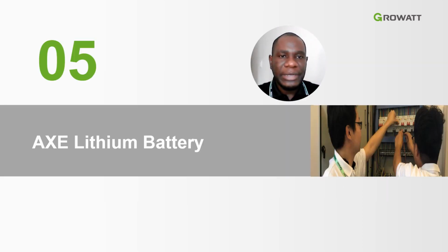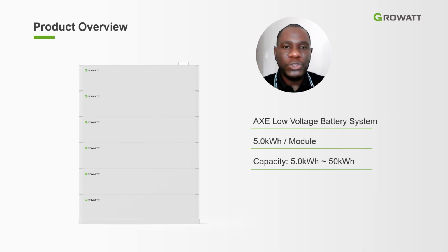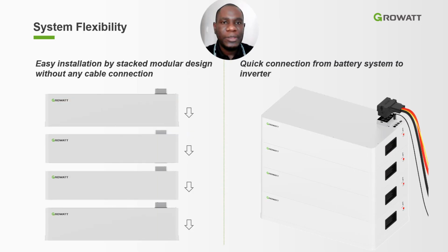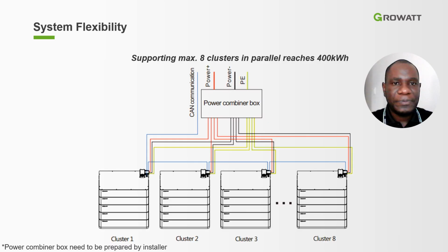The AXE lithium battery, as I mentioned before, each module has a capacity of 5.0 kilowatt hours, and you can have a cluster of up to 10 of these modules, which goes up to 50 kilowatt hour battery capacity. And this is how you connect the batteries together. Direct connection between each module. You simply put one module on top of each other. There is direct connection. You have your positive and negative from the module that is on top of all the modules. Then those two cables, your positive and your negative, go to your inverter, together with your communication cable for your BMS.